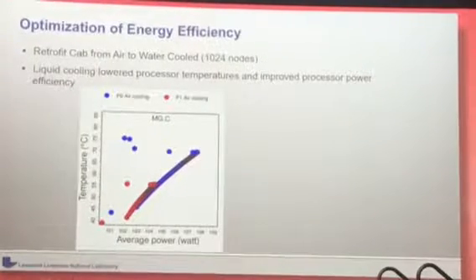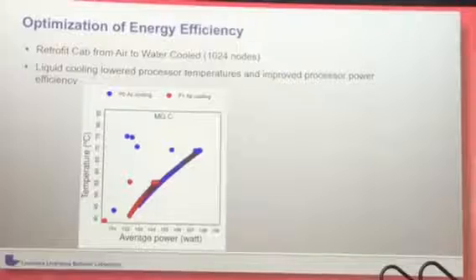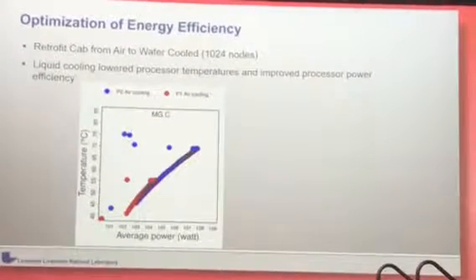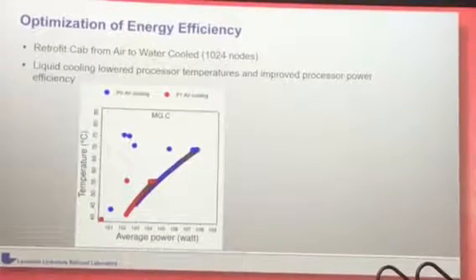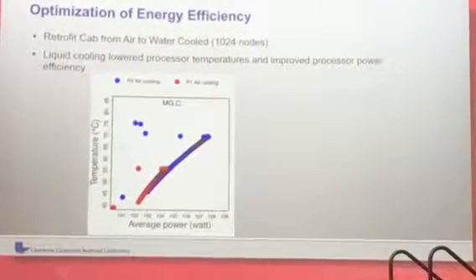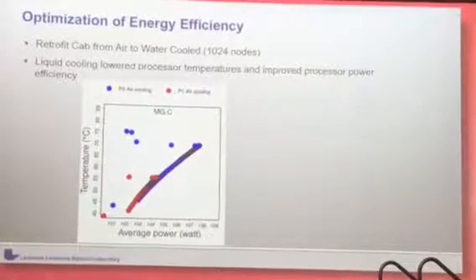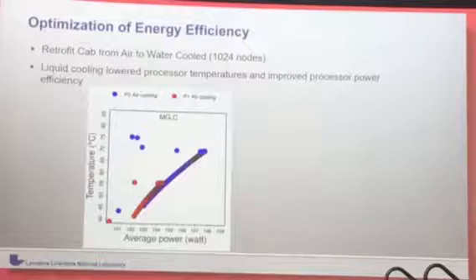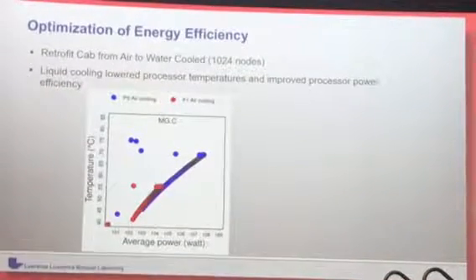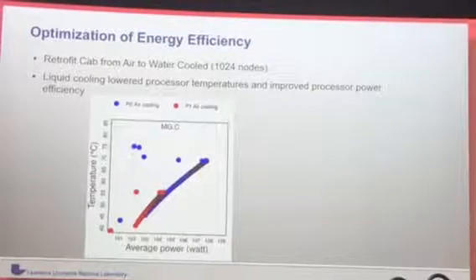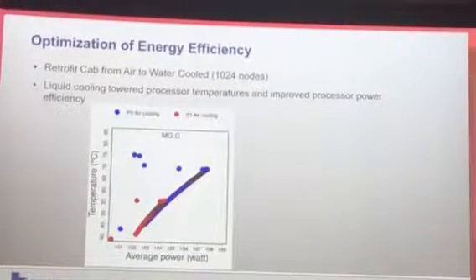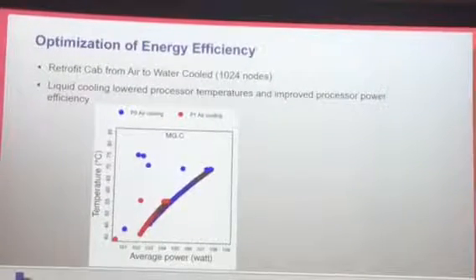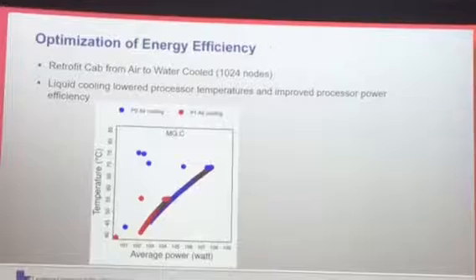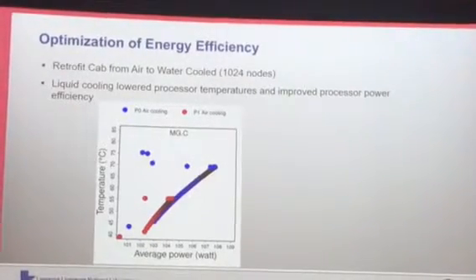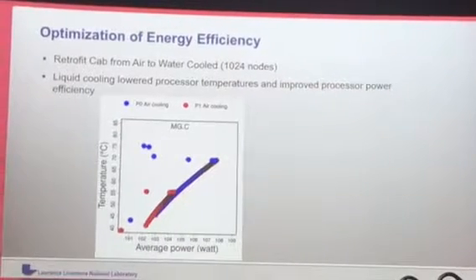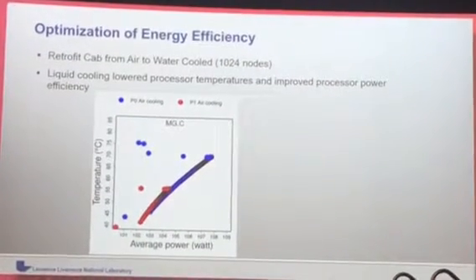So one of the neat things we had the opportunity of doing is looking at a system that was just air-cooled and looking at it when we modified it to make it water-cooled. So this is the node temperatures for a system called CAB. It's 23 racks, about 100 kilowatts. And it shows basically, in the blue is the node that's closer to the inlet fans, and then the red is a little farther into the rack. But you can see it's linear, and as the temperature rises at the node, more power is needed to do an average run. There's a few outliers that are probably due to manufacturer variabilities with the fans.